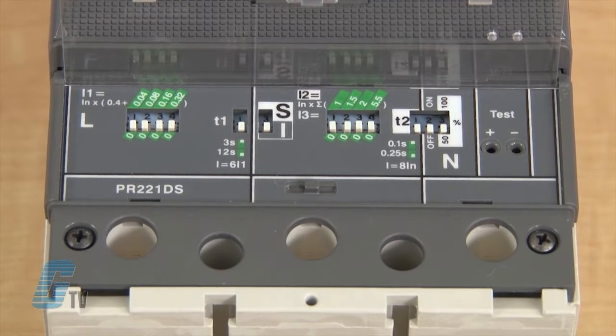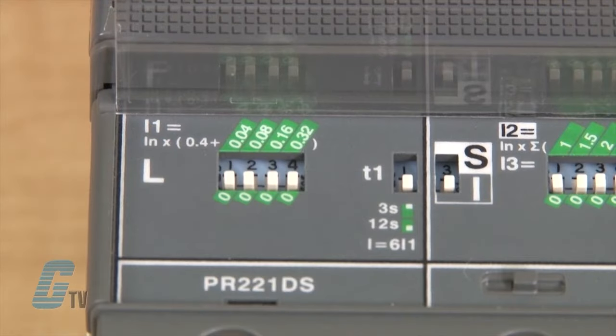My first set of dip switches is labeled L for protection against overloads. Here I can set my tripping threshold which is set to 0.4 of the maximum current rating of the circuit breaker when all the dip switches are set down.